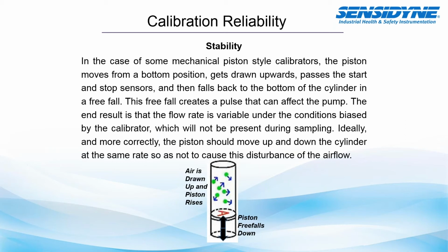So as I mentioned, in the case of some mechanical piston styles, the piston moves from a bottom position. It gets drawn upward. It'll pass a start sensor and a stop sensor. When it falls to the bottom of the cylinder in a free fall, this free fall will create a pulse wave that can affect that pump. The end result is that the flow rate is variable under these conditions, and it will bias the calibrator, which will not be present during the sampling. So in other words, when you disconnect the pump, it's actually going to be running at a smoother rate than it would be when it was influenced or biased by the calibrator piston itself.